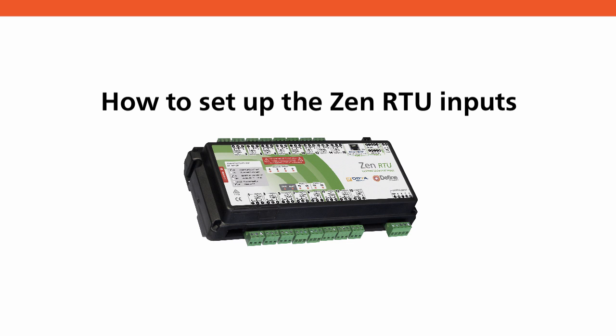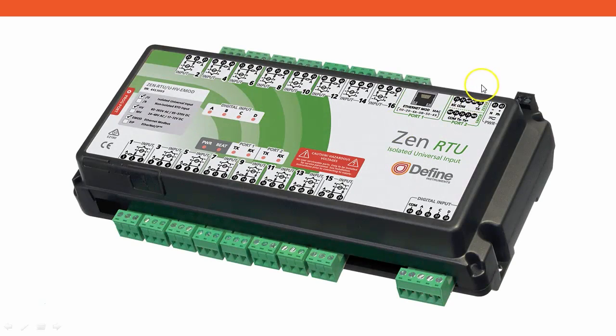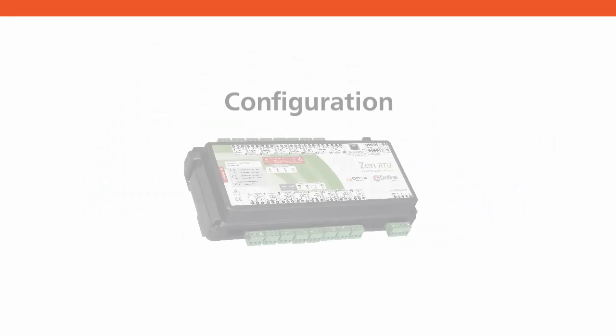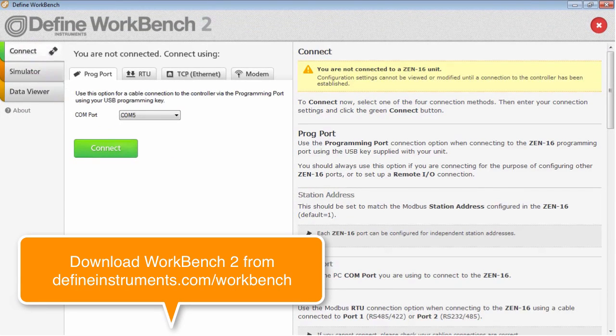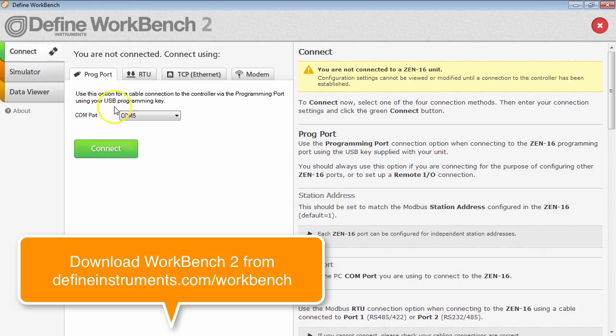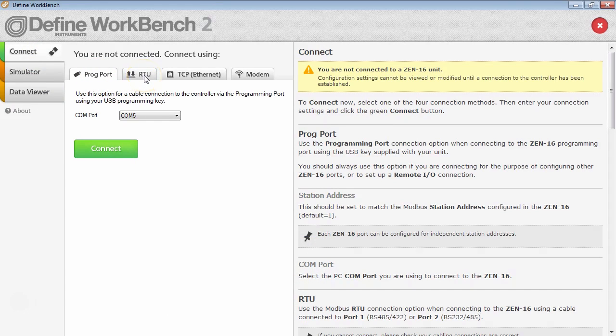I want to talk now about the setup of the Zen RTU inputs. This can be done either by connecting to the instrument through the RS232 port or the Ethernet port if you have Modbus TCP. But more commonly it would be configured through the programming port at the end of the Zen RTU here. Configuration of the Zen RTU is done using our WorkBench 2. You would connect through this page using the programming port, the 232/485 port, or the Ethernet port if you're using Modbus TCP.